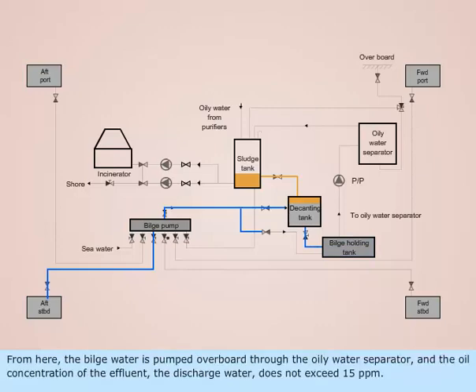From here, the bilge water is pumped overboard through the oily water separator and the oil concentration of the effluent discharge water does not exceed 15 ppm.